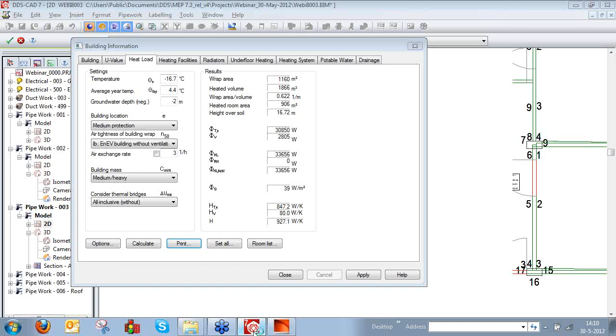So from the heat load, when the U values are correct, we can say I would like to have the one calculated, minus 16.7, and we have to consider whether these are good surroundings for this building. Do we have protection? For example, nearby multiple offices, or are we on free land? What kind of system are we using for our materials? Is it very light built, or is it medium built with durable material? From the options, we can use the EN 12831 for doing the heat loss calculation. This is an international norm, and by pressing calculate we can see the influence directly.